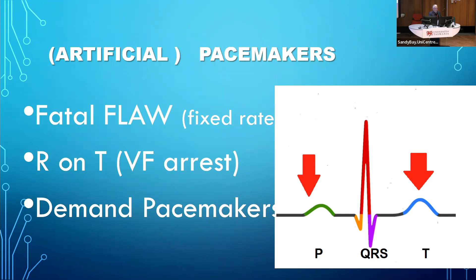Now, a normal pacemaker, when it works, is supposed to apply an electric pulse to mimic what the heart normally does. So you apply an electric pulse here where the P wave should have been, and it causes a normal contraction, the QRS complex. But if you inadvertently try and pulse and pace the heart when it's trying to recover, it'll go into VF. It's called an R on T phenomenon, and if your heart's got no conduction at all, it's not a problem, but if some of your native heartbeats are getting through, then they can conflict and your pacing beat can actually put you into a fatal situation. So the current pacemaker designs avoid this risk by both sensing and pacing down the same wire. And these wires are inserted onto the inside of the heart, not the outside. So in a demand pacemaker, which is what these are called, if the heart is beating, the pacemaker does nothing. But if for any reason the heart misses a beat, then the pacemaker drops a beat in, so the heart rate is maintained.